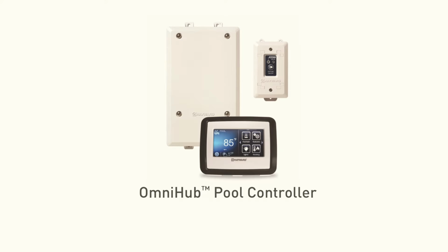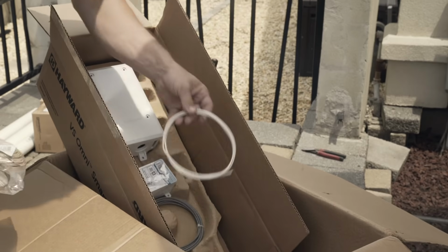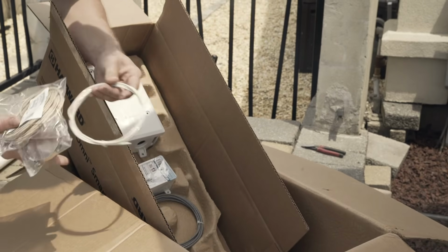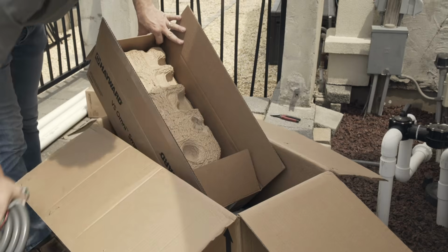The VS Omni display, wiring hub, and smart relays are contained in rain-tight enclosures that are suitable for outdoor mounting. The wiring hub and smart relay is designed to mount vertically, with the knockouts facing downward. Do not mount either inside a panel or tightly enclosed area. When selecting a location, note that the standard cables supplied are all 15 feet long, except for the pump's power whip, which is 6 feet long.